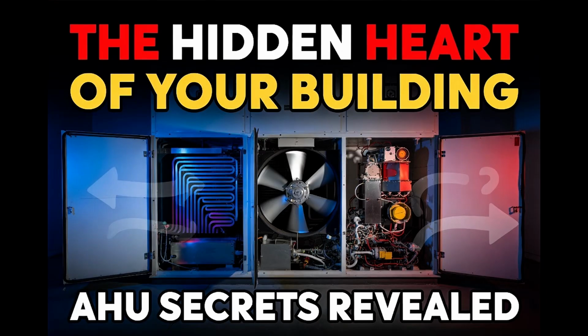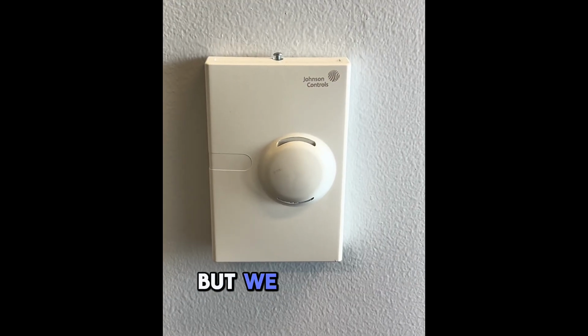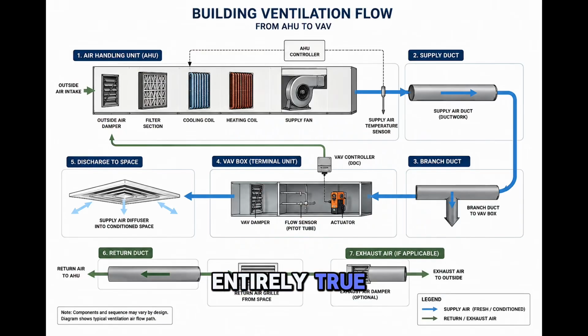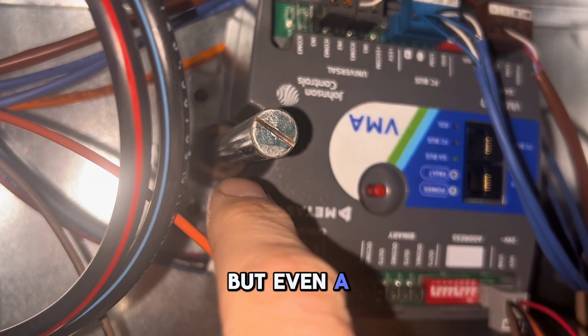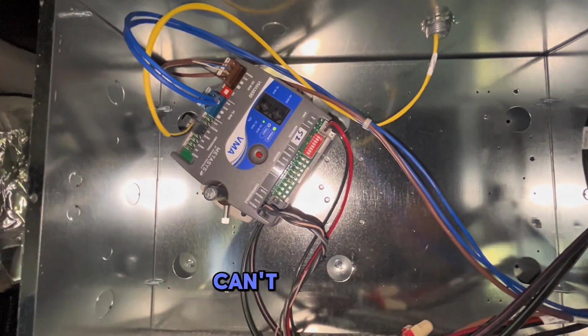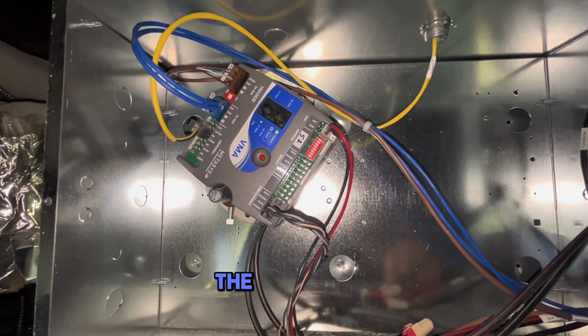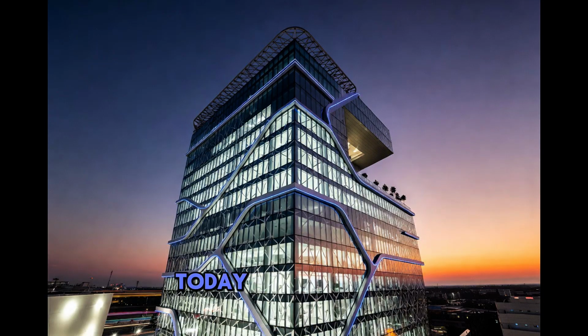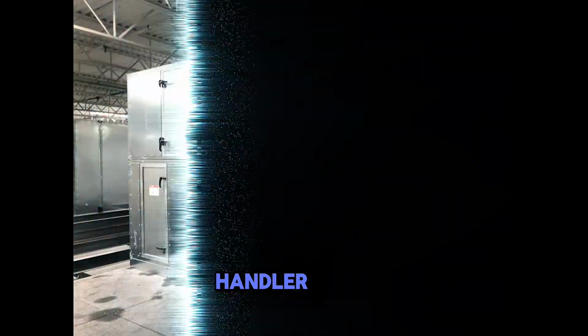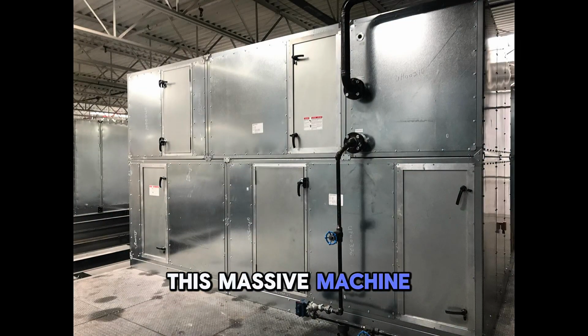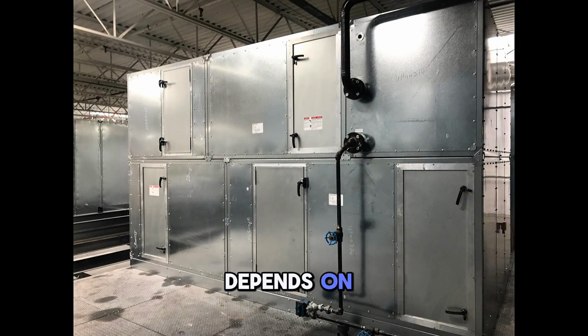You've been told your thermostat controls the room, but we already know that's not entirely true. You've seen inside a VAV box. But even a perfectly working VAV can't fix the real problem if the heart of this system is failing. Today I'm cracking open the air handler unit, this massive machine that everything else depends on.